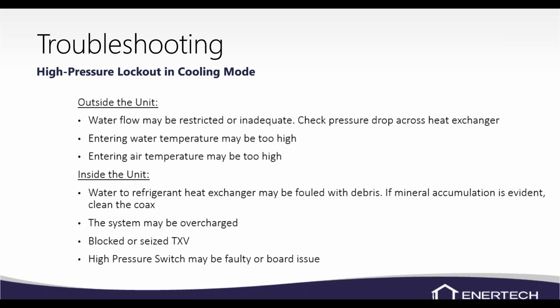Usually our lockout boards are pretty reliable. The high pressure switches, they fail occasionally. A lot of times I see them fail. The collar on the top of them kind of breaks, and it just loses the signal through it. It can't make, it doesn't realize that it's still closed.